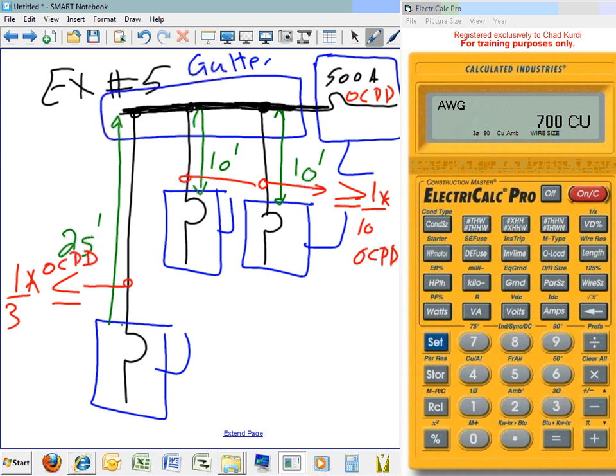So what's the advantage of the 10 over the 25? The 10 can get you a smaller conductor tap, right? 1/10 of a number is smaller than 1/3 of a number, right? I hope so. Everybody knows that. Why is 10 better than 25? The 10-foot rule allows you to tap a smaller conductor from a bigger conductor than the 25-foot rule does. Okay, with me, guys? So these two taps have to have a conductor size greater than or equal to 1/10 of the overcurrent device. Is it a tenth of the physical size or the ampacity? A tenth of the, they call it the long time pickup of the circuit breaker. So if this is a 500 amp and it's set to trip at 500 amp, then you multiply by 500 amp, because later on these can be adjusted, guys. It's the ampacity of the overcurrent device.